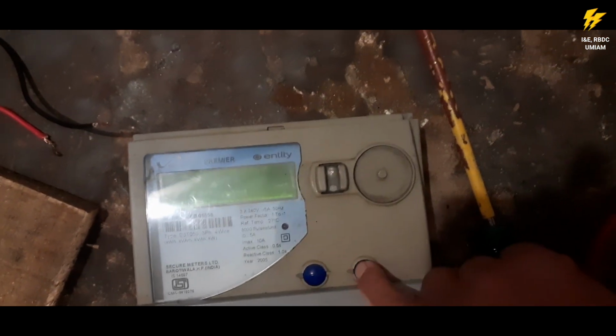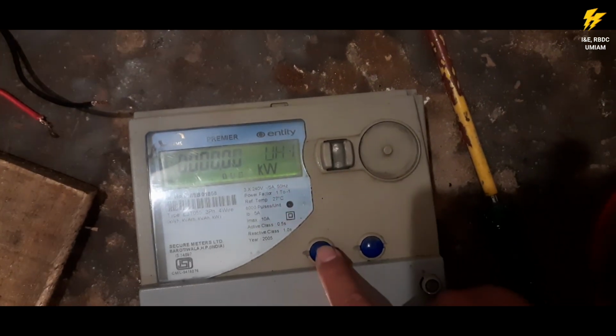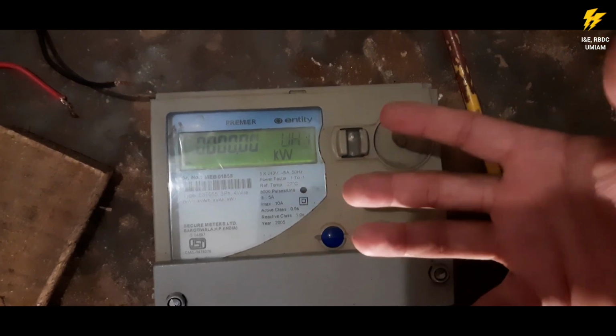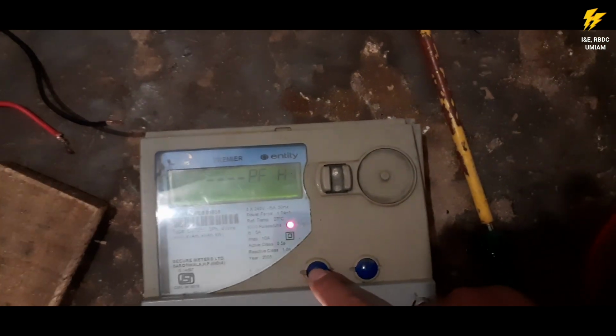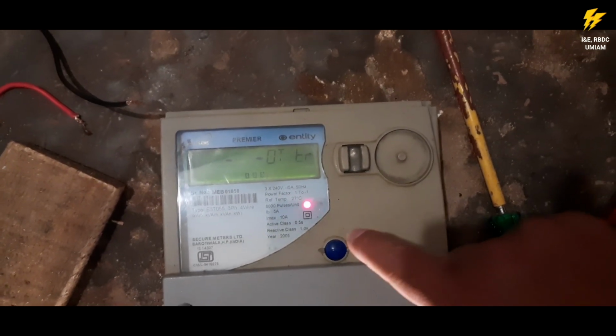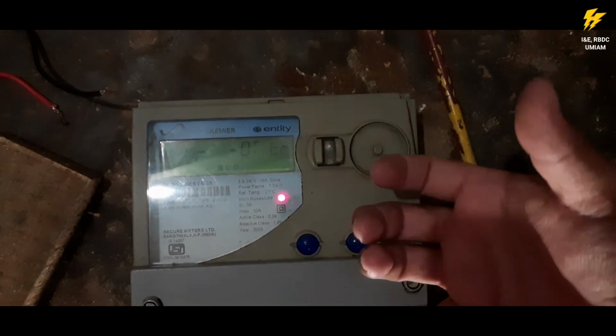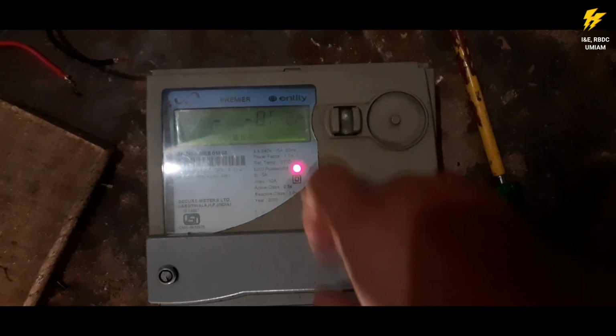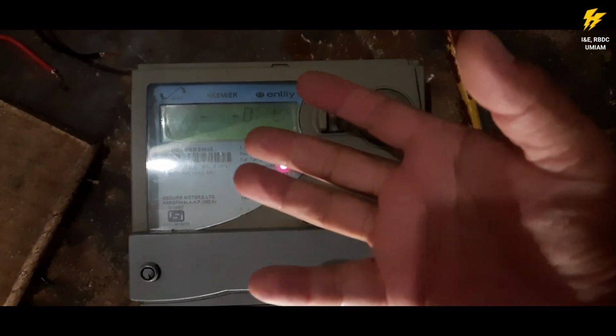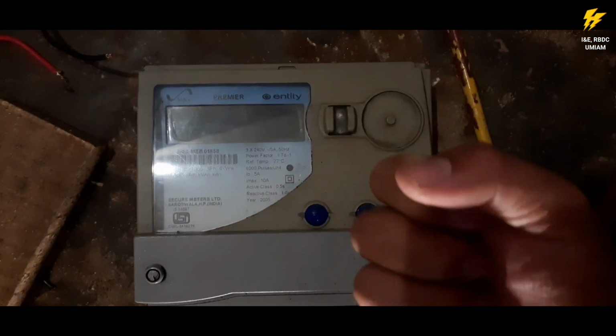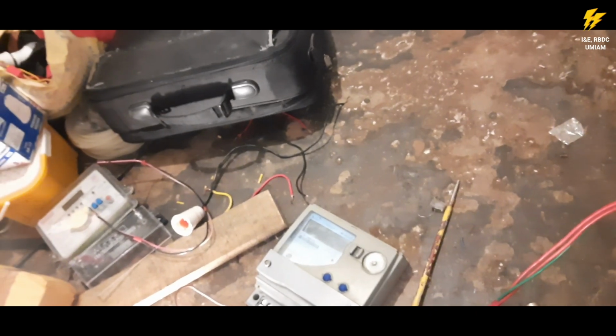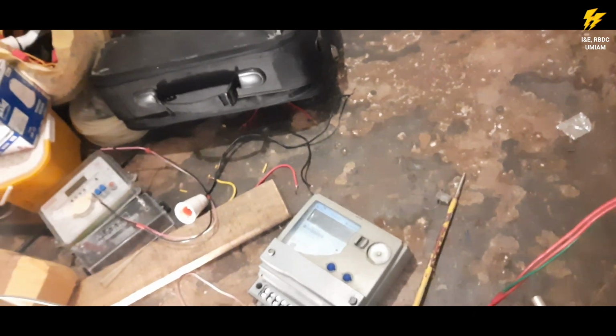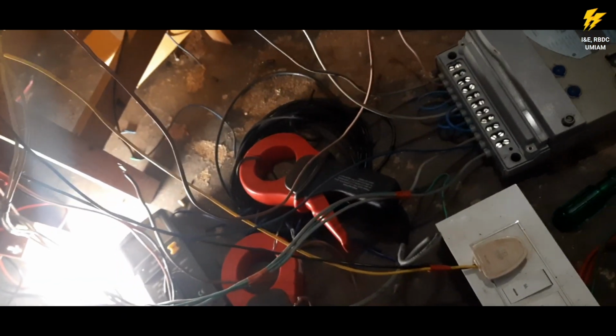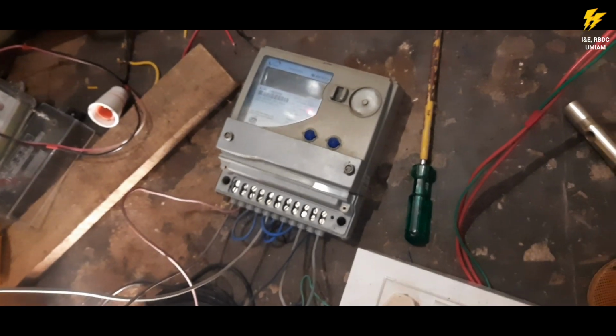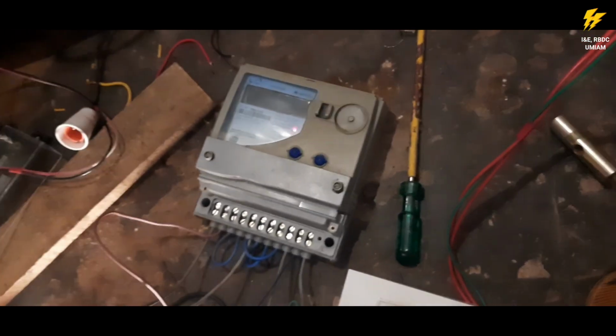All right, by pressing this, you have to keep pressing continuously for 3 or 5 seconds, then it will automatically reset, right? You don't have a maximum demand now. All right, so that's why the first button is always used. You have to go to the maximum demand and keep pressing this continuously, not 5 seconds, 3 or 4 seconds, then the maximum demand will automatically reset. Okay, so this is what you do. It has to be done by an authorized personnel. Whenever you go for reading, then he resets, so that he'll know the maximum demand of the preceding month when you come next time for reading. So this is how the taking of the required readings is done for this secure meter. All right, so thank you.